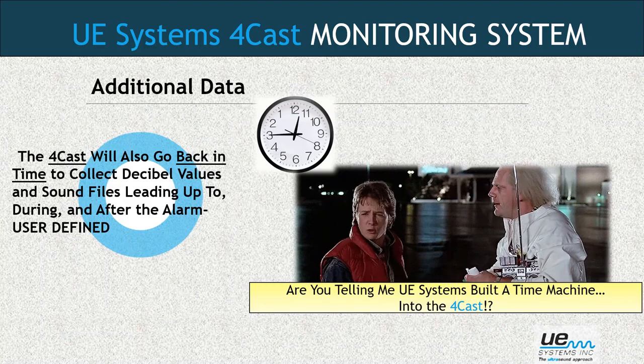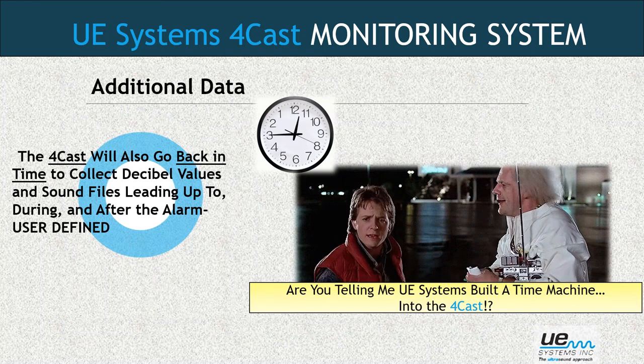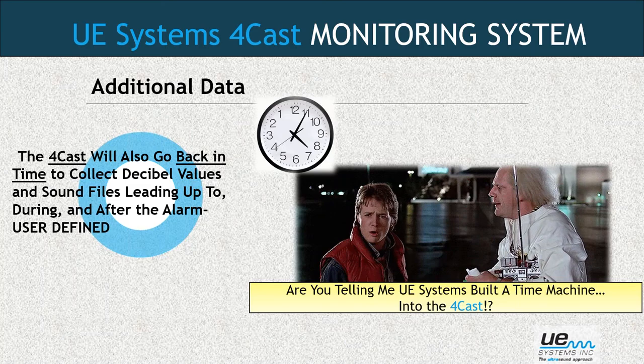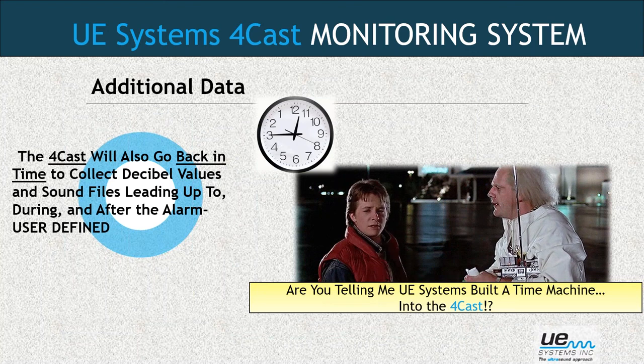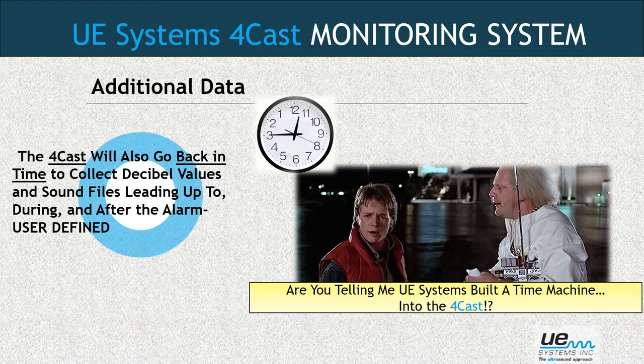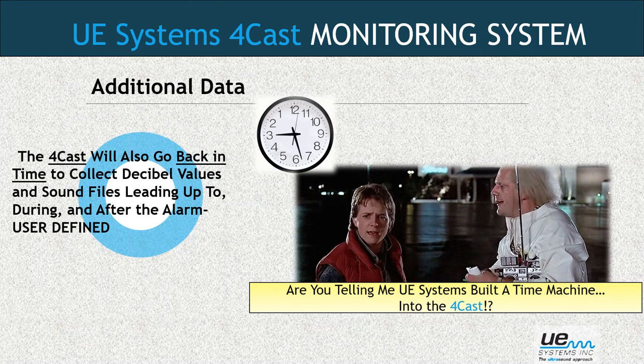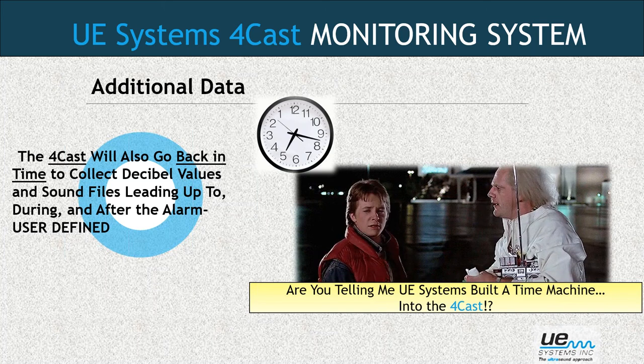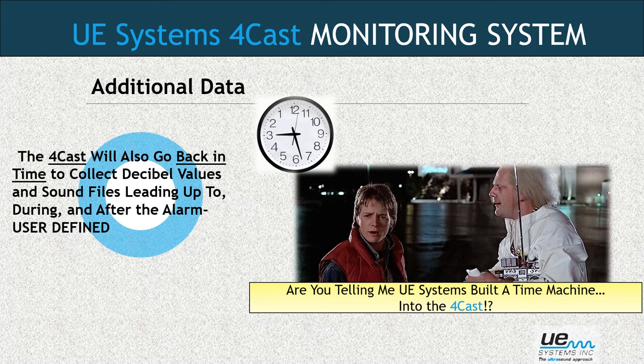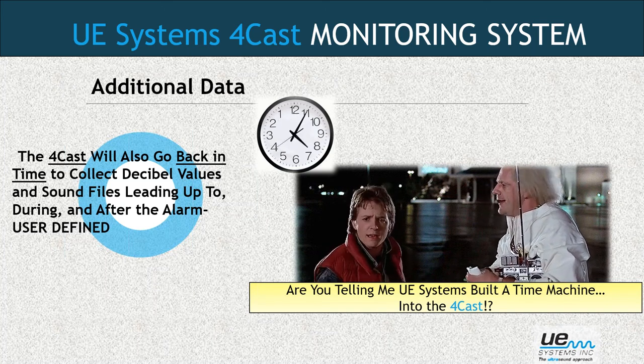The 4Cast lets you go back in time and collect decibel values and sound files leading up to, during, and after the alarm. All of this is user defined inside of DMS software, so you can go in and, based on the criticality of the equipment and its failure history, determine if it goes into alarm, we need to start storing, or go back and see what happened every day leading up to that alarm.